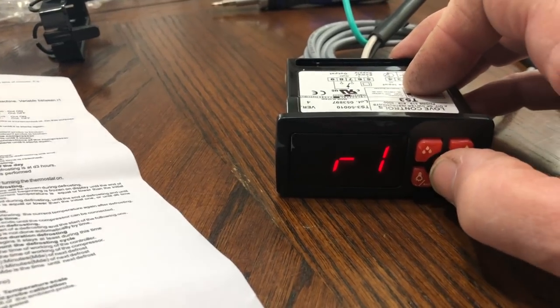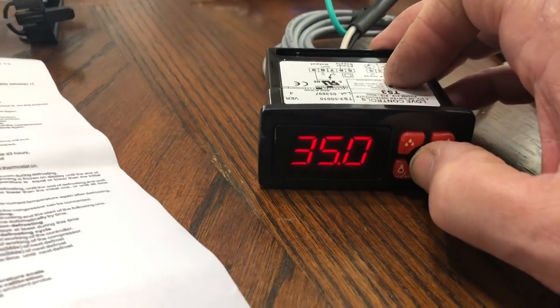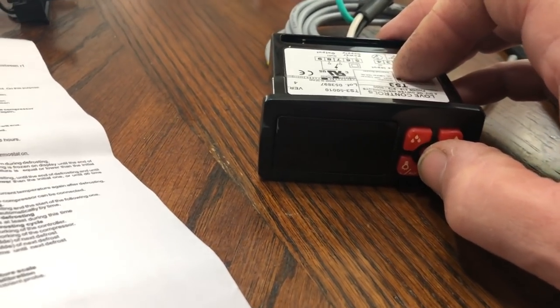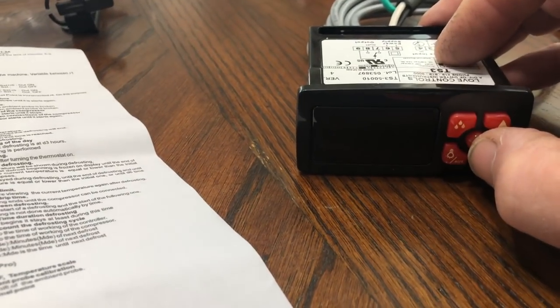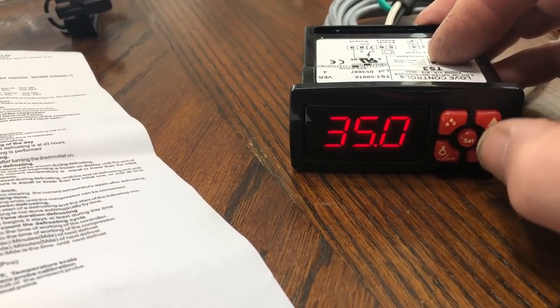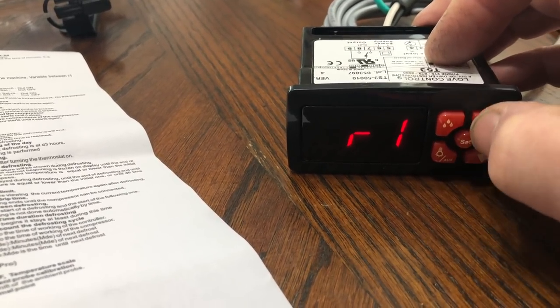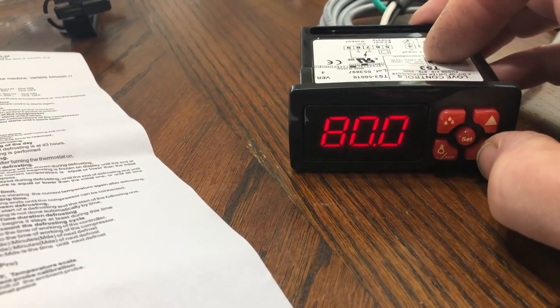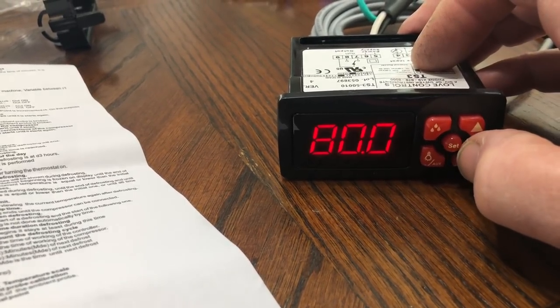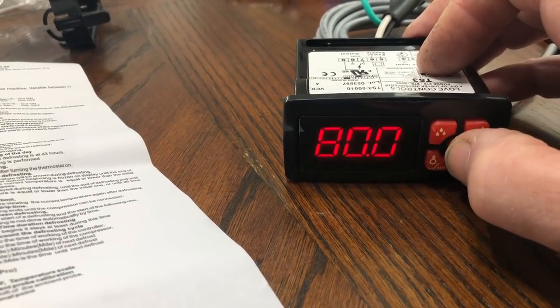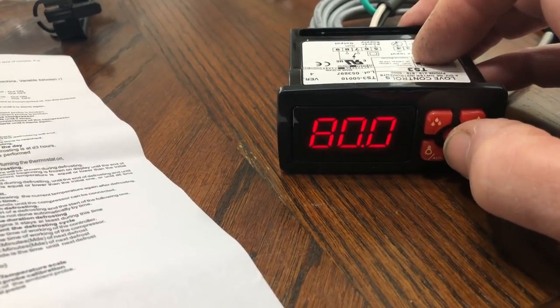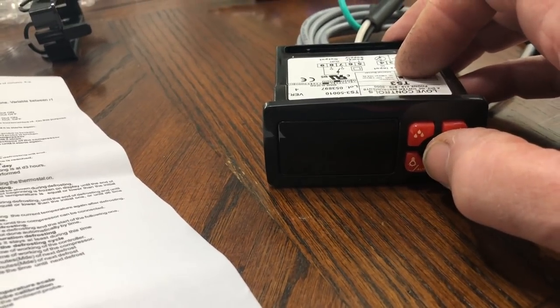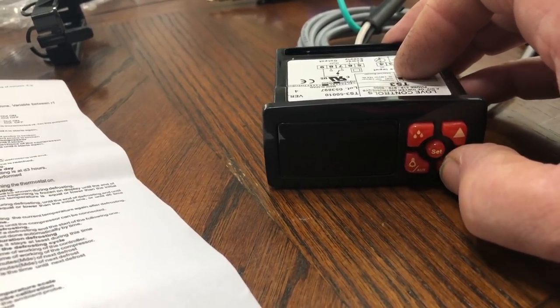Back to set. The next selection is R1, minimum set point. So I had it set for 35. So they couldn't turn it any colder than 35. The next one R2 is the maximum. I had it at 80. So during troubleshooting, you could play with the thermostat and see if your contacts are opening or closing. If this was on a reach-in type or a walk-in type box, you probably want to set that a lot lower.